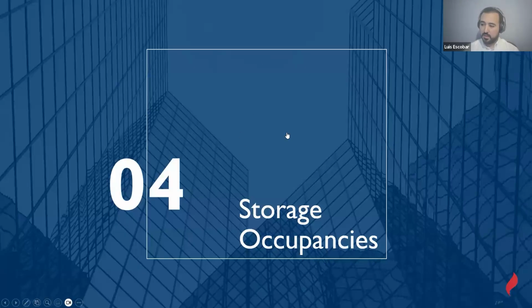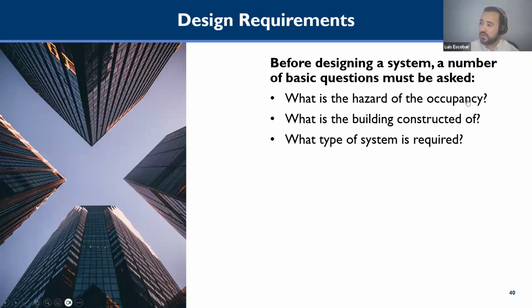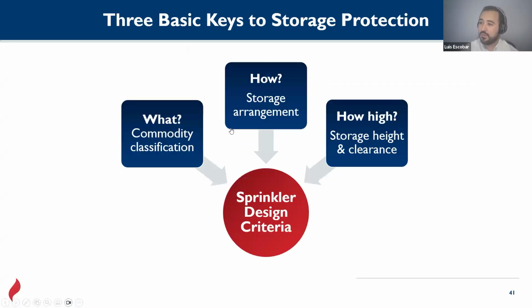Storage occupancies are the most critical design for our industry, I would say. What is the hazard? What is the building constructed of? And what type of system is required? What, how, and how high? What are we going to store? Plastic, concrete, dust, wood. How? Racks, high pile, in shelves. How high is the storage? If it's going to be a 5-foot pile or a 25-foot rack, the scheme of protection will be totally different between those two examples that I just gave you.